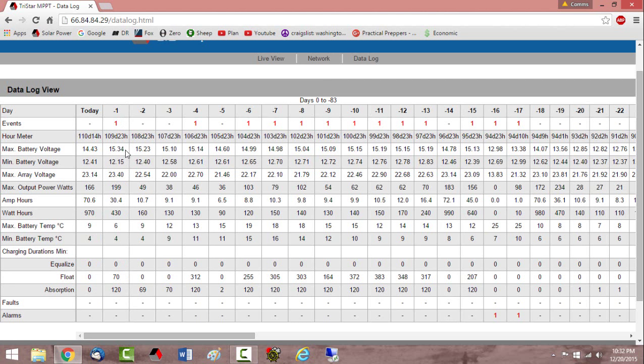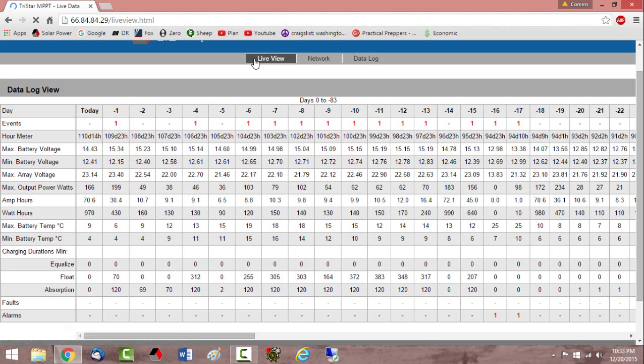Now that's a little higher because the batteries were cold last night. It got down to 4 degrees Celsius, almost freezing. So the charge controller with their remote temperature sensor automatically compensates for the reduced efficiency in the batteries because of the lower temperature. So this is my charge controller. This is another system I have out there that I can remotely monitor.